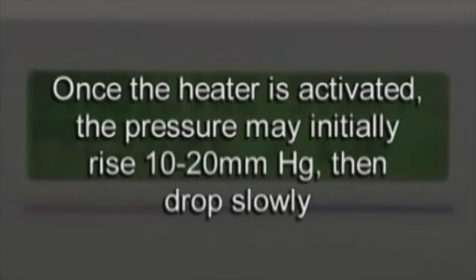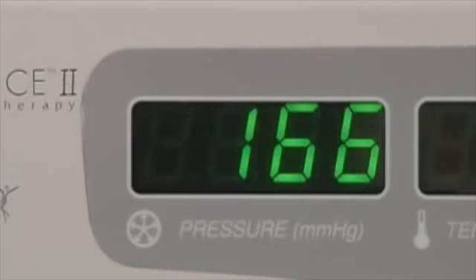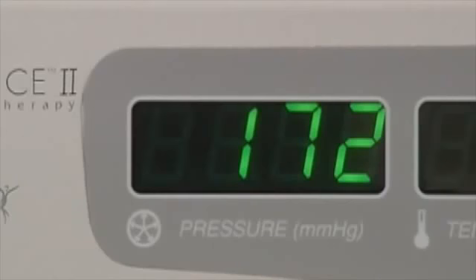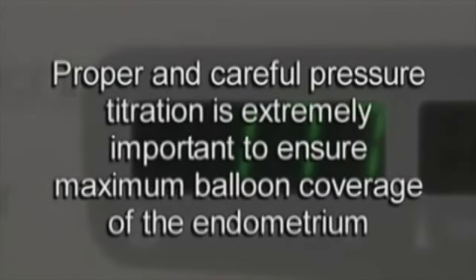Note: once the heater is activated, the pressure may initially rise 10 to 20 millimeters mercury. The pressure may then drop slowly for the remainder of the procedure. Once a pressure of 160 to 180 millimeters of mercury has been stabilized for at least 30 seconds, therapy can now be initiated. It is no longer necessary to maintain contact with the fundus. Note: proper and careful pressure titration is extremely important to ensure maximum balloon coverage of the endometrium.